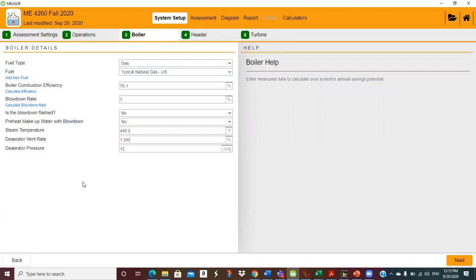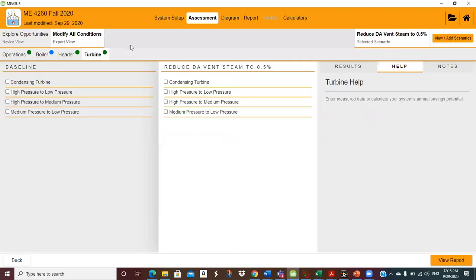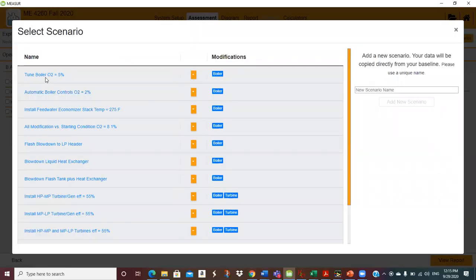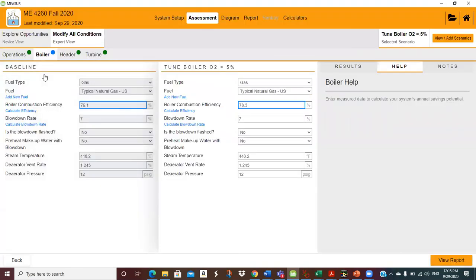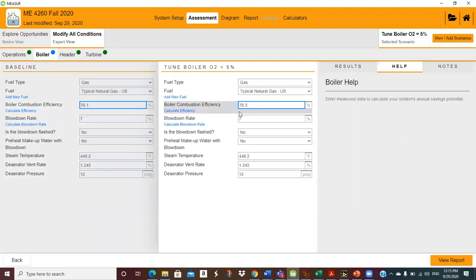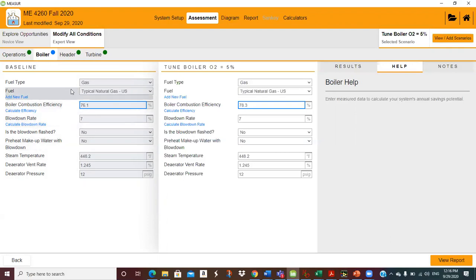This is the first scenario: tuning the boiler to 5% oxygen. So we're going from 76.1% to 78.3% efficiency. When you've got a lot of these scenarios, sometimes you wind up running numbers that you don't think you're running, so it's always good to take a little time and make sure. I think that's correct. Let me check the header.